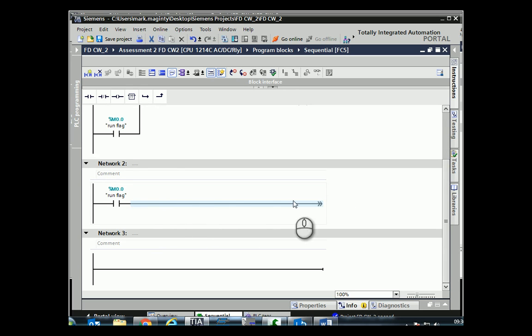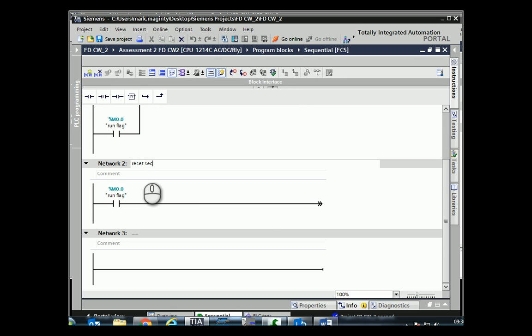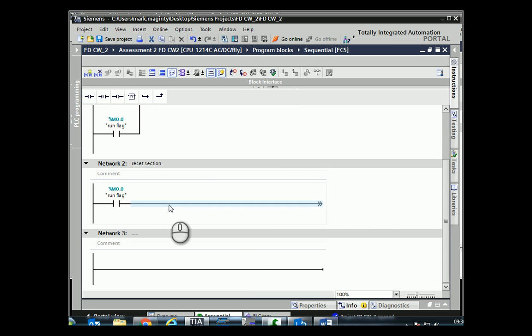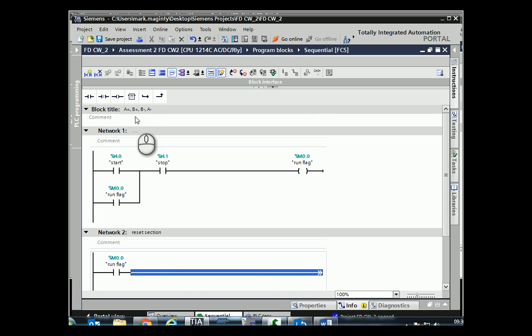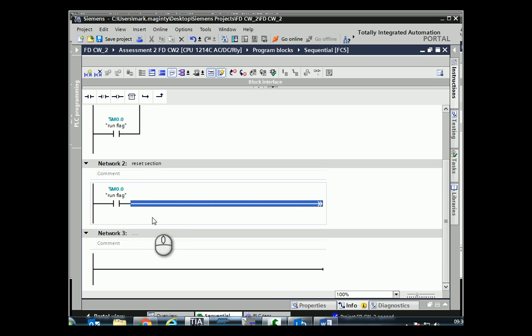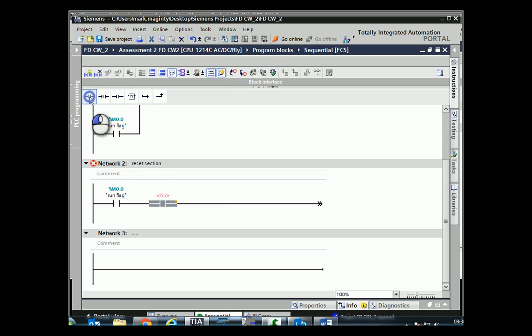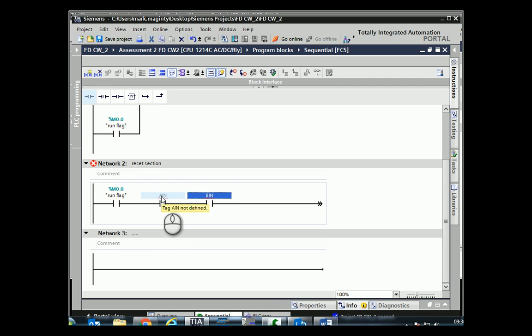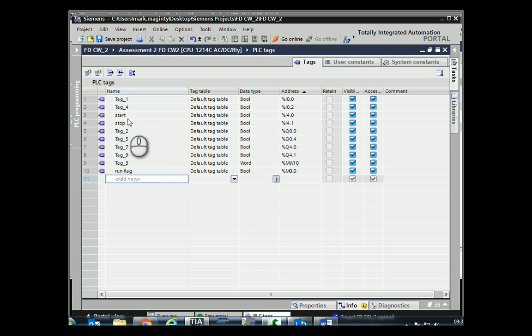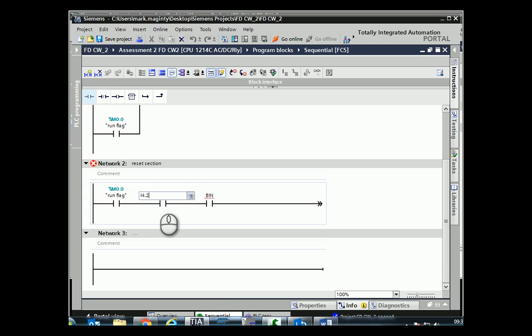This next line is to do with the reset. The machine will only allow the sequence to start when it's in a certain position. We need to detect that position — reading off the A-in and B-in sensors, we can assume both cylinders must be retracted to start. I'll label those as I4.2 for A-in and I4.3 for B-in, and go into the tag table to label those up.